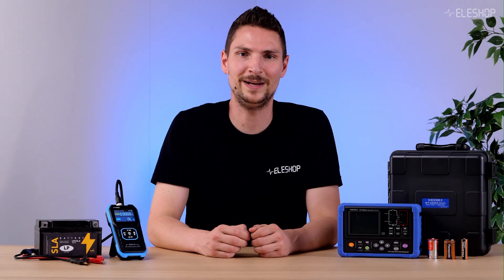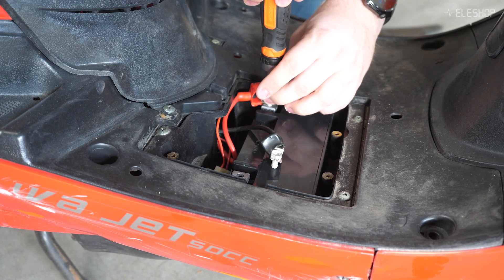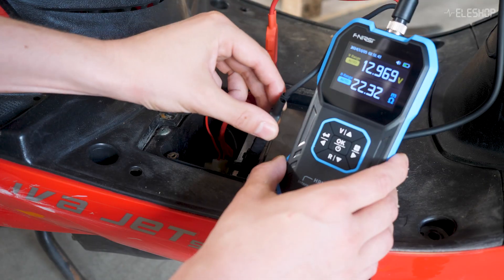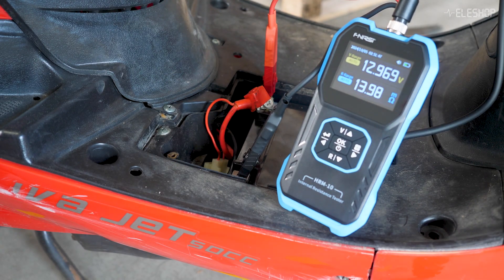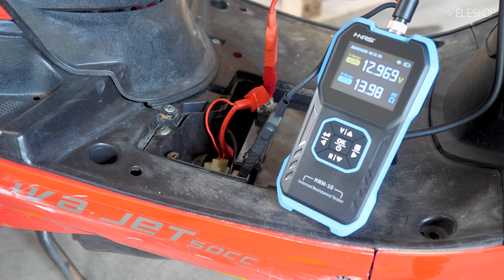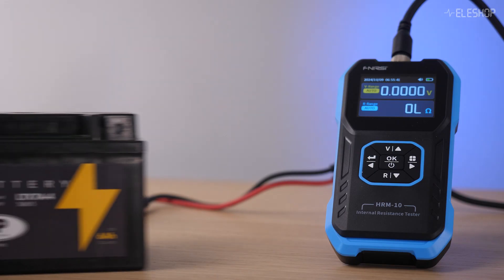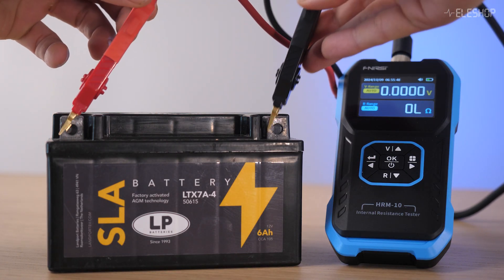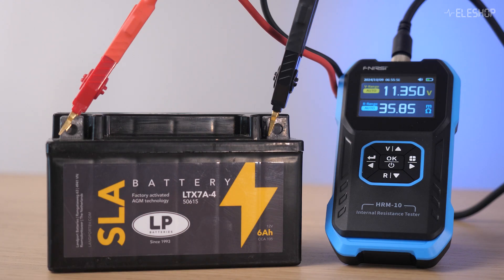Let's quickly demonstrate the testing of a battery. First, we measure a 12-volt 7 amp-hour battery using the FNIRSI HRM-10. You can see the display shows the internal resistance in milliohms and the battery voltage at the same time. We measure 14 milliohms and 13 volts DC, which is great since this is a new battery. Now let's measure this old battery — a 12-volt 6 amp-hour battery. Here we measure 35.8 milliohms, indicating that this battery is indeed at the end of its life.